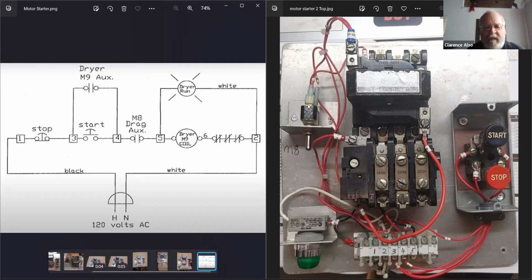If you put the tip of your test probe right there, what are you expecting? 120 after you hit the start. There you go. And now I'm saying you've got 0 volts. What does that tell you? That tells me the M8 auxiliary is bad or blown.